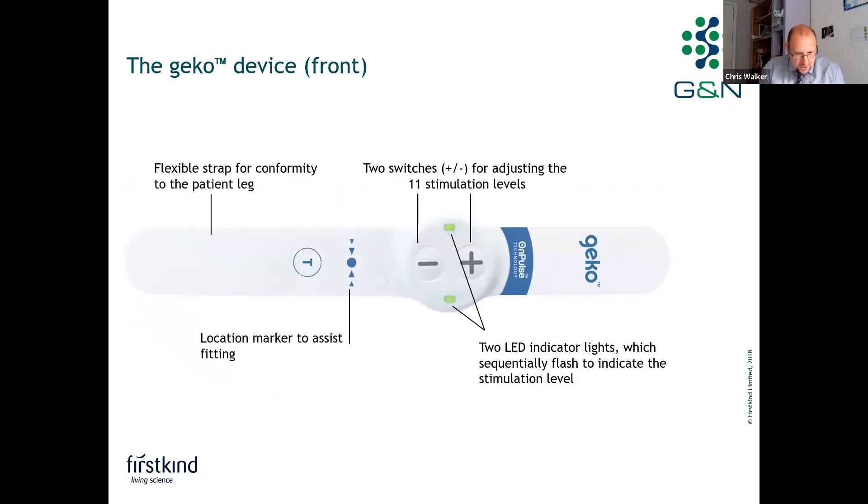On the picture of the device here, on the front of the device is a location marker line, and that helps to assist with the fitting of the geko device. That line goes over the head of the fibular bone, where the common peroneal nerve is closest to the surface. There are two switches on the device where you can adjust to one of the 11 stimulation settings required to activate the nerve and instigate that muscle reaction. There are also two indicator lights on the front, which flash every second a number of times to indicate the level or setting you are on.